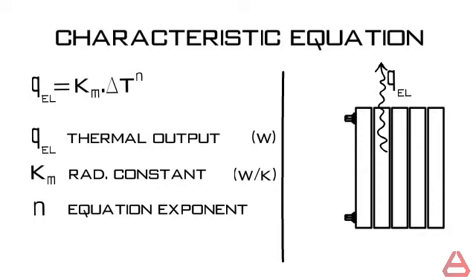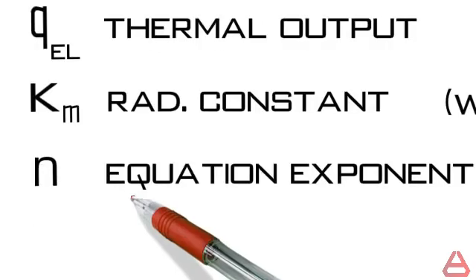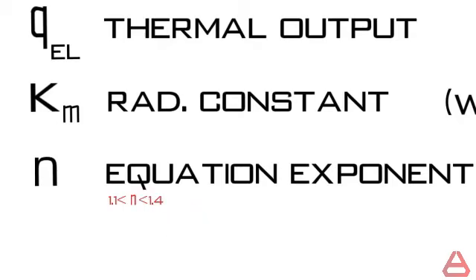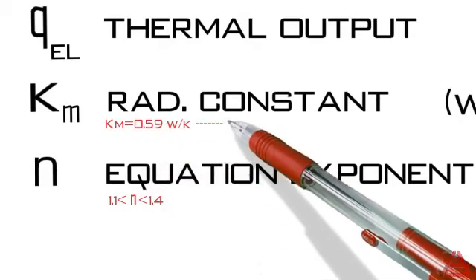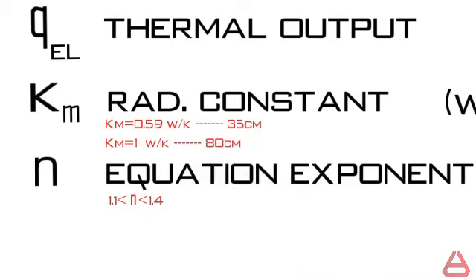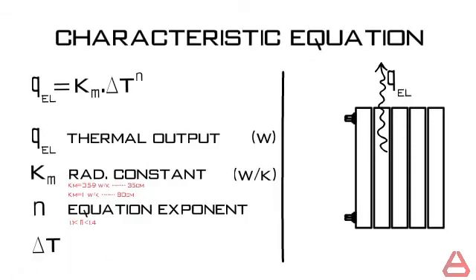It is a unitless exponent. n falls between 1.1 and 1.4 and Km is close to 0.59 for a 35cm radiator element and up to 1 for an 80cm element. Delta T is equal to TR minus T average and its unit is Kelvin.